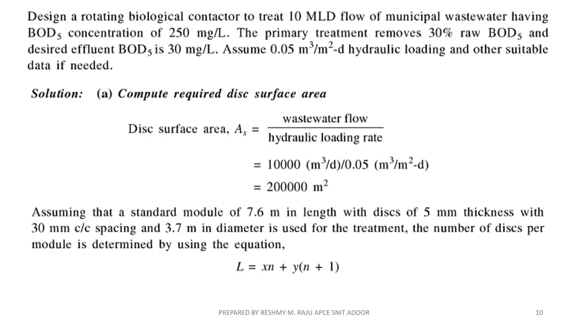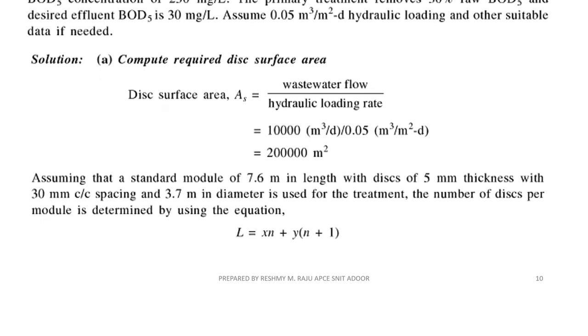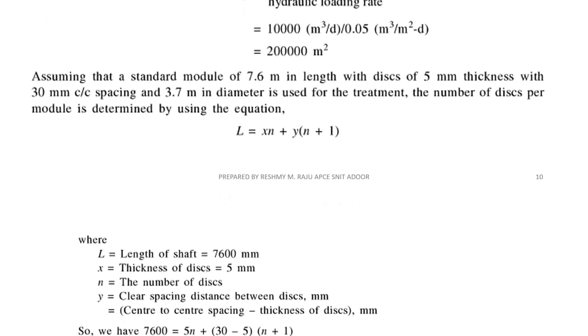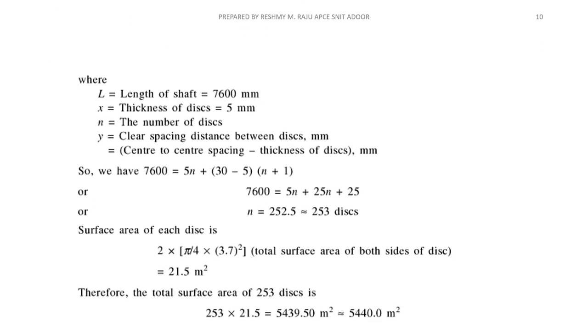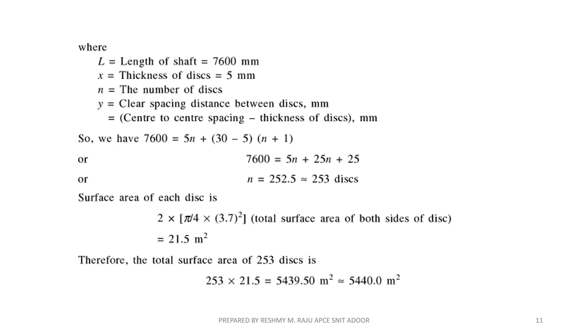For the design chamber, we use the number of disc equation: L = x·n + y·(n+1), where the length of the shaft L is 7.6 m (i.e., 7600 mm), x is the thickness of the disc equal to 5 mm, n is the unknown number of discs, and y is the clear spacing between discs. Solving this gives us 253 discs per shaft.